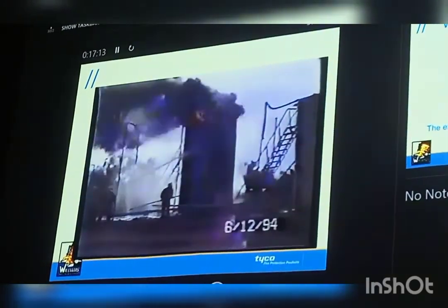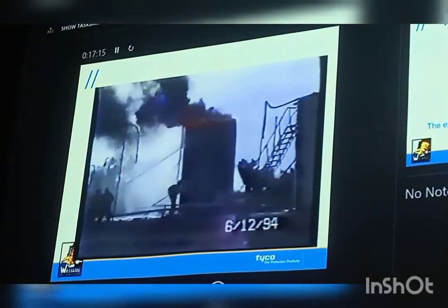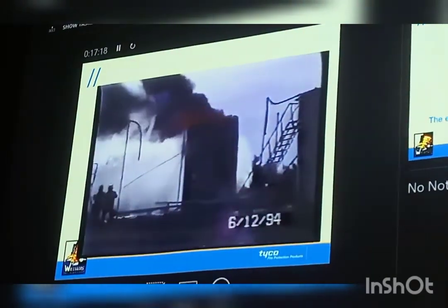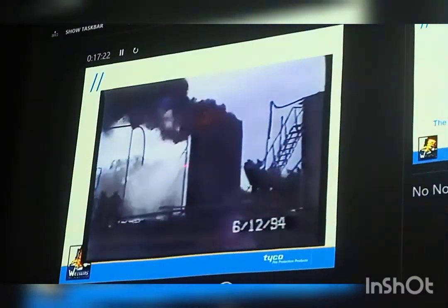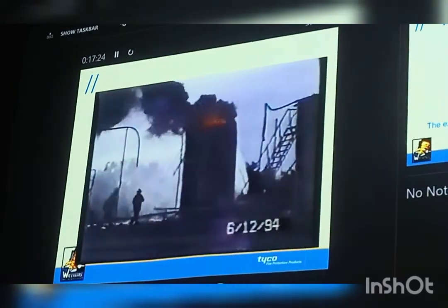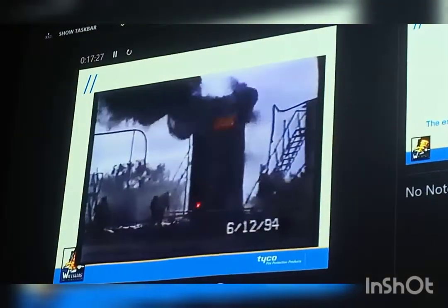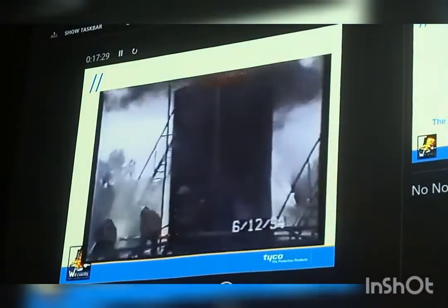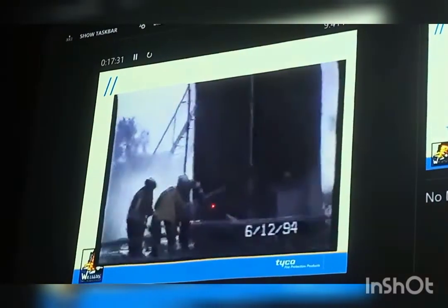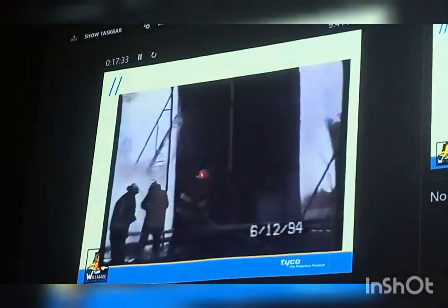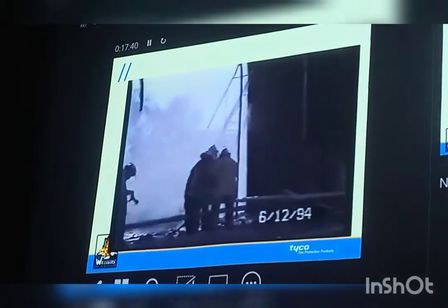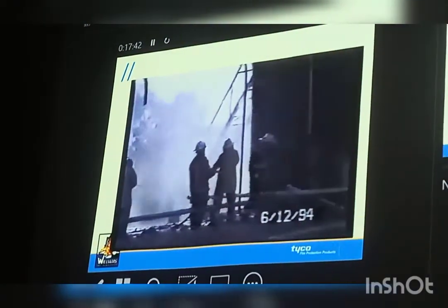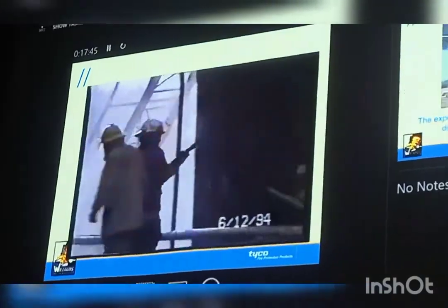This is just a small header tank with crude in it. A government fire department has responded to it. What you see here, they're just trying to cool one side of the tank, but we discussed this the other day. They're setting up something similar to a gooseneck nozzle over the top, and they're going to put foam on the line into that gooseneck.